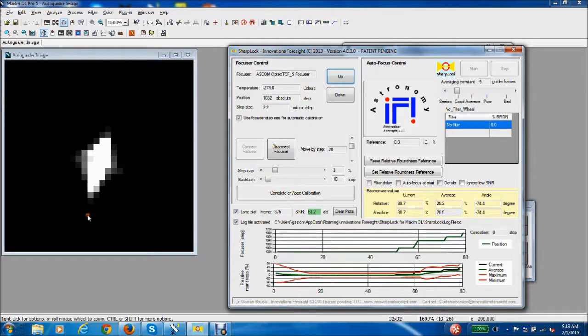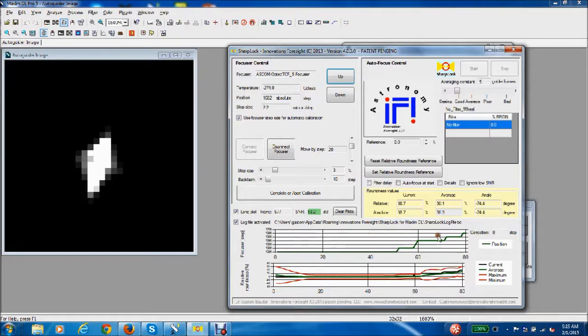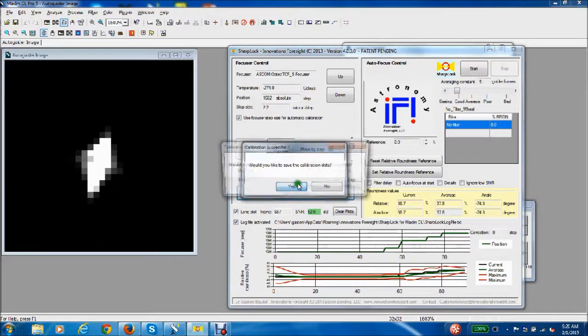Moving more means increasing again the roundness, and you see how much the star is elongated now. And the absolute roundness is higher than it was before. You see the statistics with the maximum, minimum in red, and the black value and green value showing you the average and the actual values. Okay, let's stop the calibration. Since the button is not in red, you can stop, and the system will say it's successful.